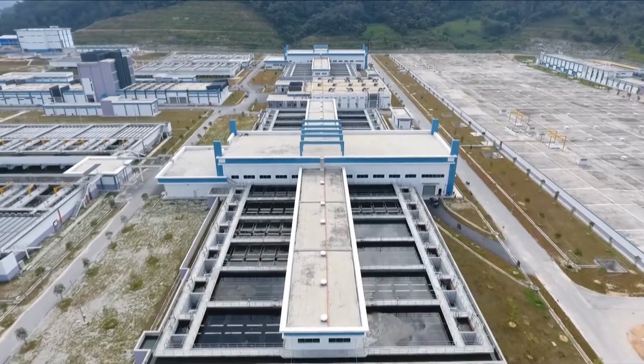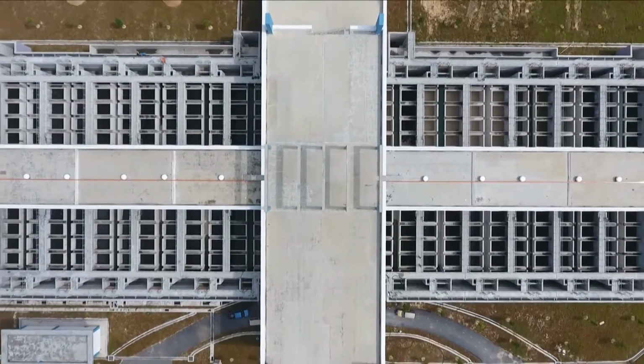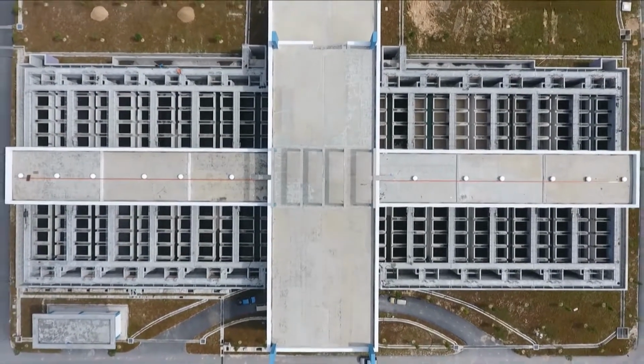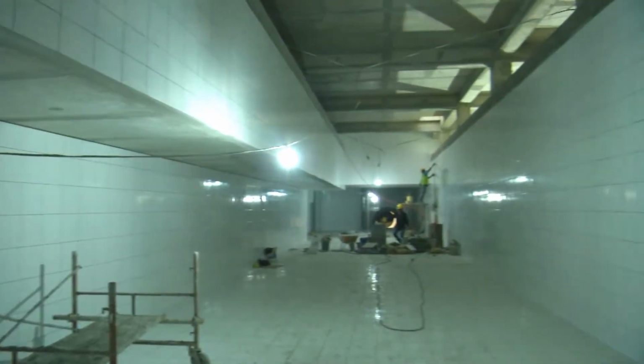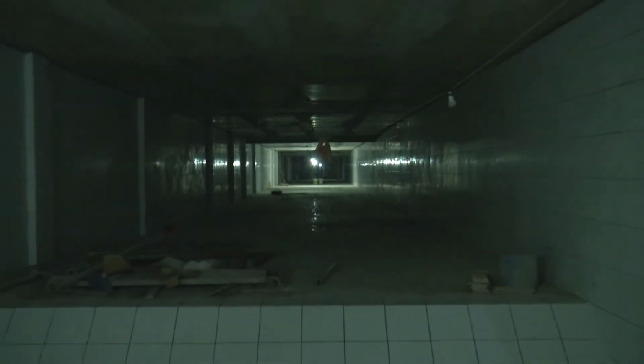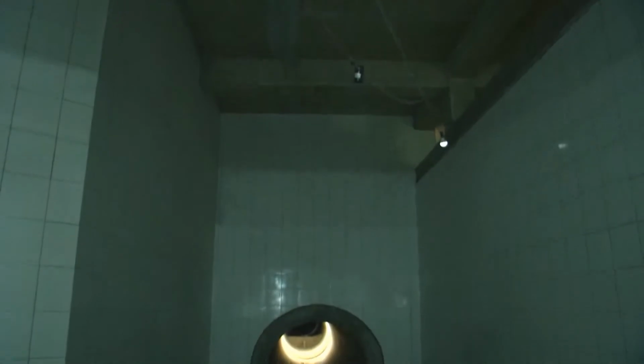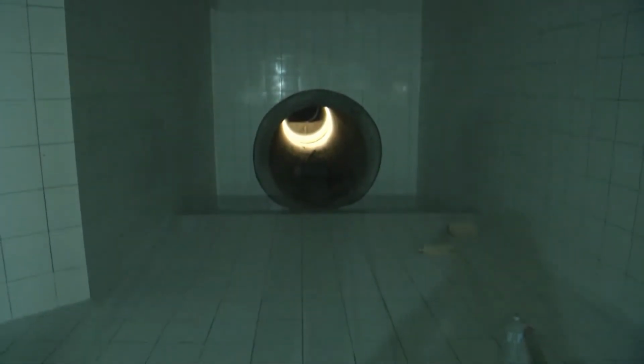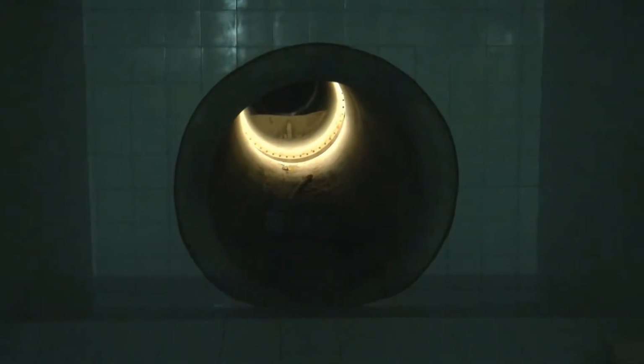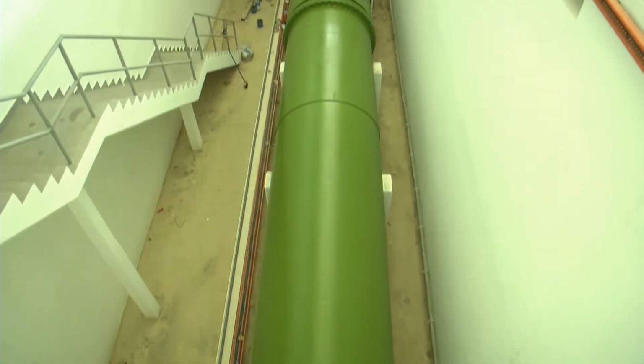Clarified water from the clarifiers is distributed into 12 filters for each substream. Filtered water is collected in the underdrain systems, which consist of a concrete false floor, and subsequently piped to a collection tank to be transferred to the clear water tank.